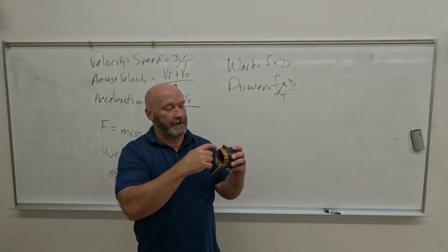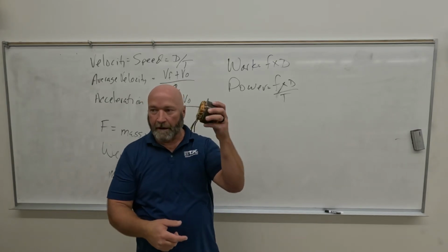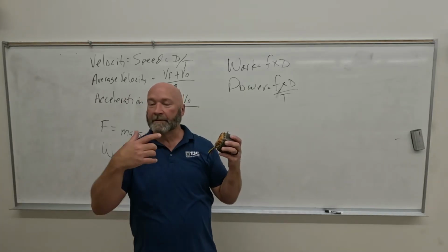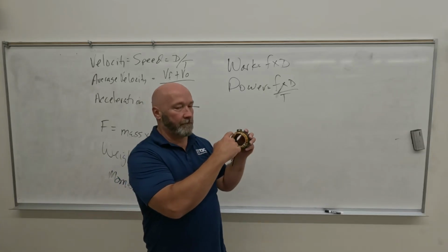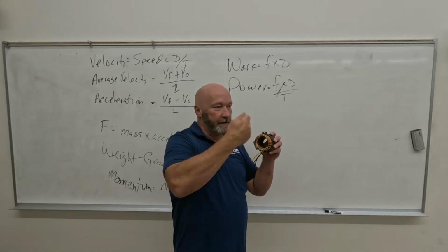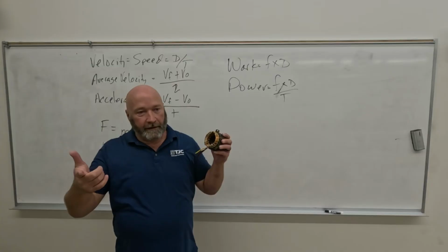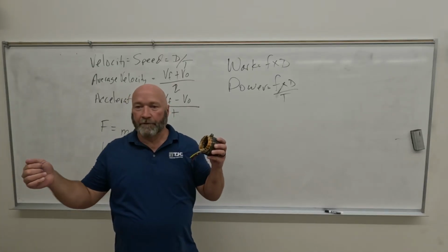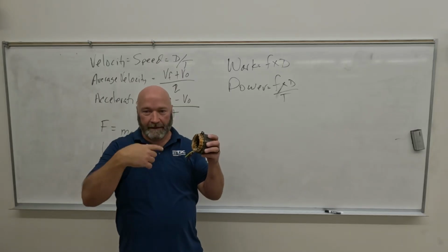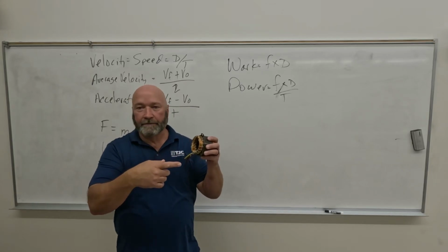And at the same time, you get alternating current going through this coil of wire. That alternating current is going through each one of these individually in a specific sequence, so it's like you're taking a magnetic field and running it around and around this way. Okay? So that's what you're hearing, a spinning of the anode whenever you rotor up. Because this is going around and around like that, it's spinning that anode. We'll get deeper into that later in the semester. But it's spinning the anode, okay?